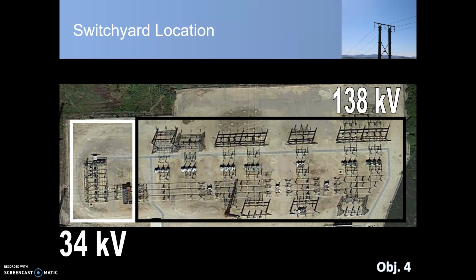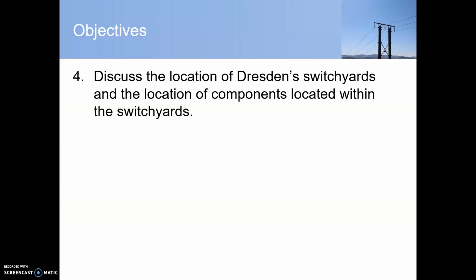Also shown on this particular photograph is transformer 10. Transformer 10 is the separation between the 138 kV switchyard and the 34 kV switchyard. It's right where the black and white lines meet on this particular drawing. The 34 kV switchyard has 3 lines that leave, and you can see those lines heading off into the west out of our switchyard.